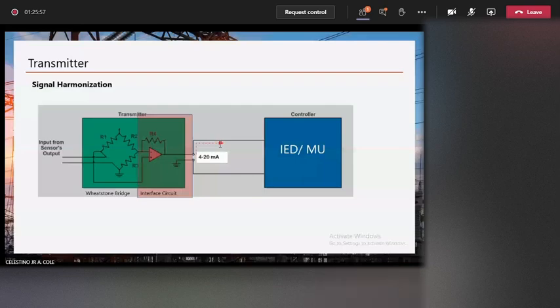So what's the difference between live zero and dead zero? For example, if the supply is lost, how would the system know whether that situation means the supply was lost, or the value being measured actually dropped to zero? It's hard for the system to recognize that—there's no way for the system to tell.